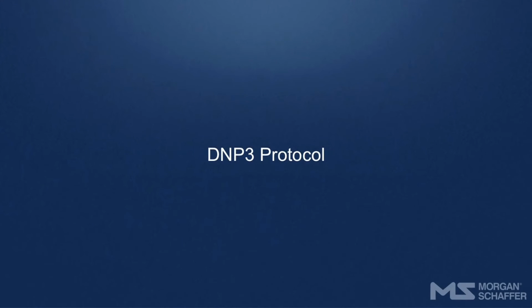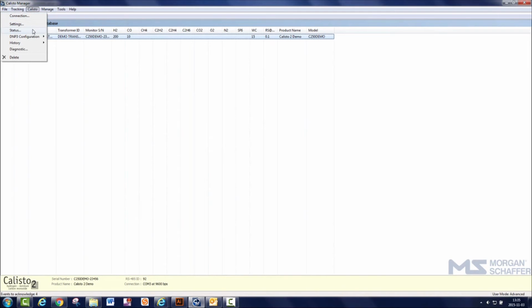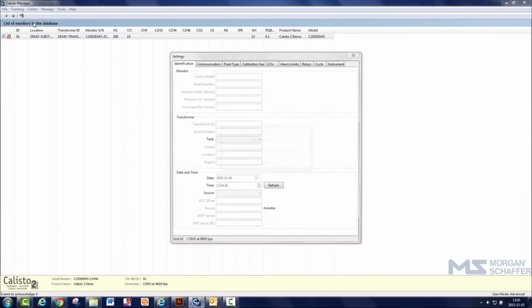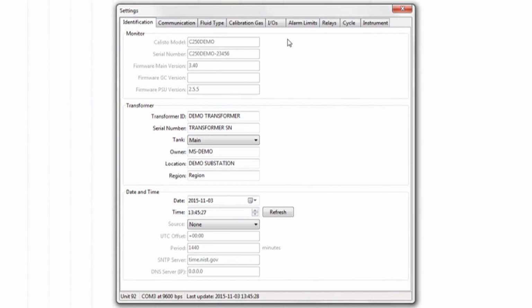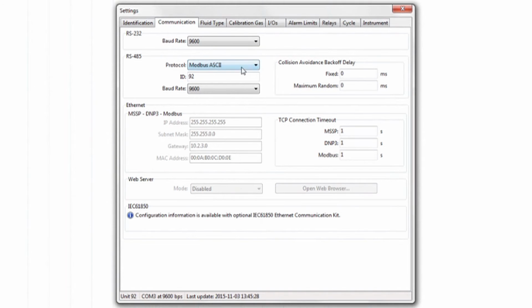DNP3 protocol. Under the Calisto menu of the main screen, the DNP3 configuration is used to configure DNP3 for RS-485 or TCP communication. Modbus protocol. The Modbus protocol can be activated on the RS-485 communication port of Calisto. Both RTU and ASCII transmission modes are supported.